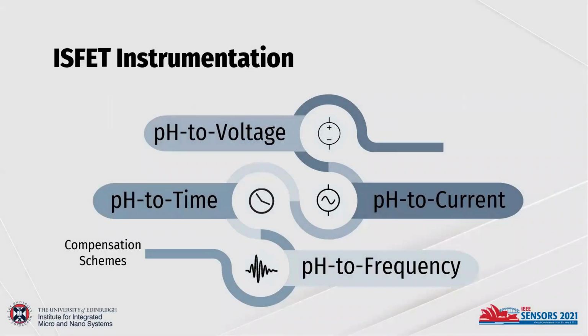ISFET circuitry falls into four categories: pH to voltage, current, time, and frequency. The most popular pH to voltage topology is the source drain follower because of its compactness and low power consumption. However, it lacks compensation schemes and it is dependent on power supply variations. Regarding the pH to current category, a CMOS current mirror and a translinear principle architecture stand out. Drift, temperature compensation, and great linearity cover their advantages, but they carry issues related to the simplicity and/or complexity of each design in terms of size, power consumption, and compensation schemes as well.